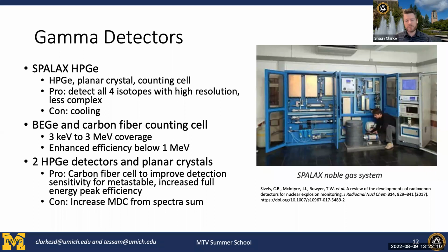So one system is focused on high purity germanium. High purity germanium is kind of the gold standard for gamma ray spectroscopy. It has excellent energy resolution on the order of tenths of a percent at cesium energies. What this allows the system to do is define these regions of interest very accurately, and thereby produce very precise count rates for the various isotopes.